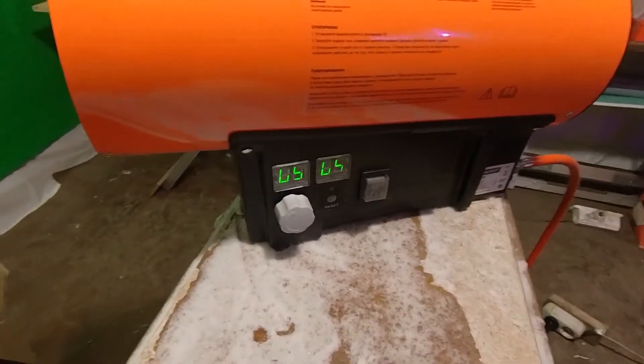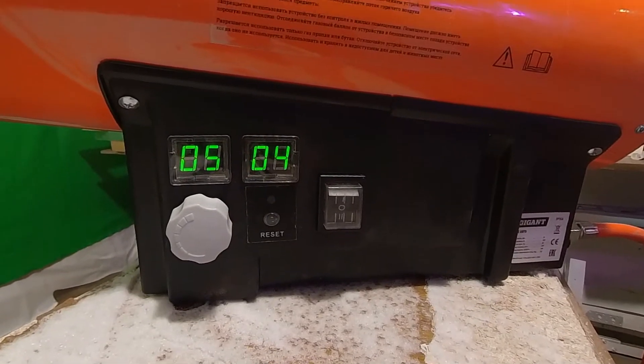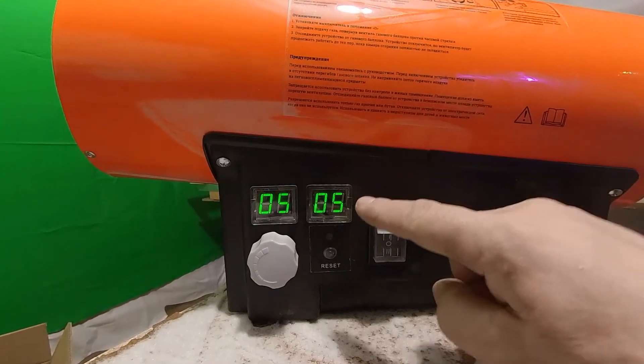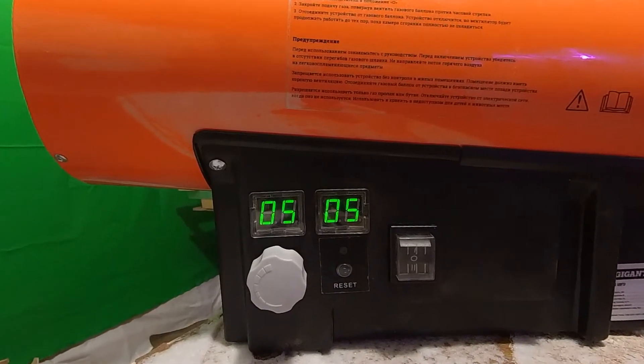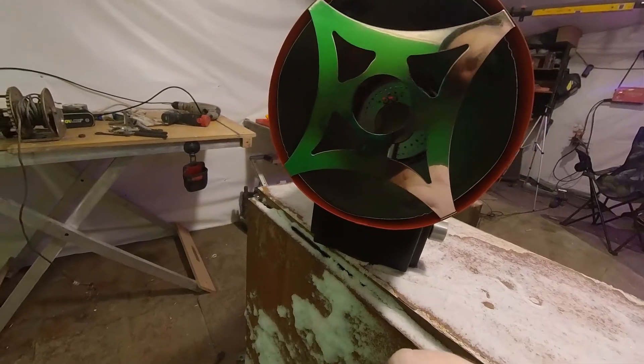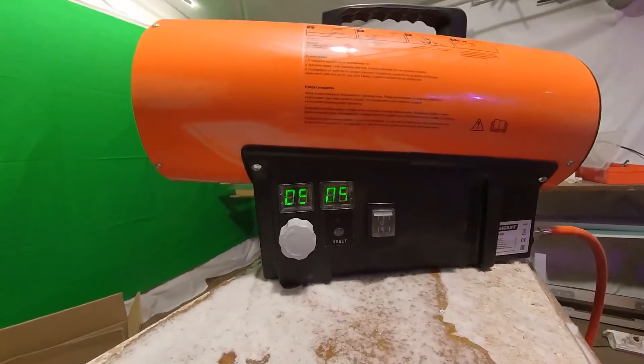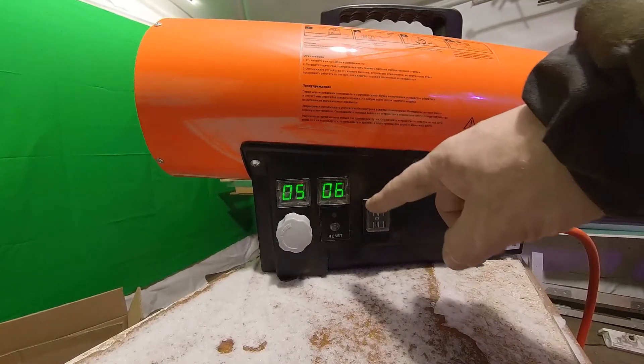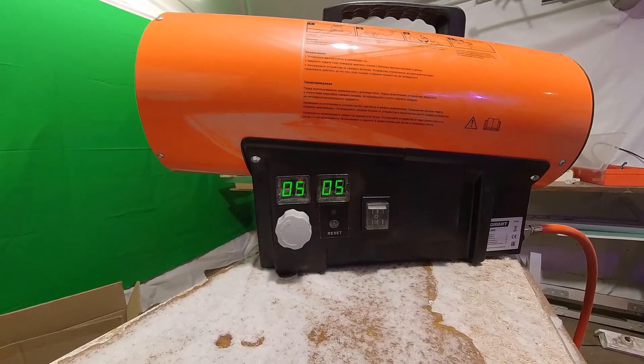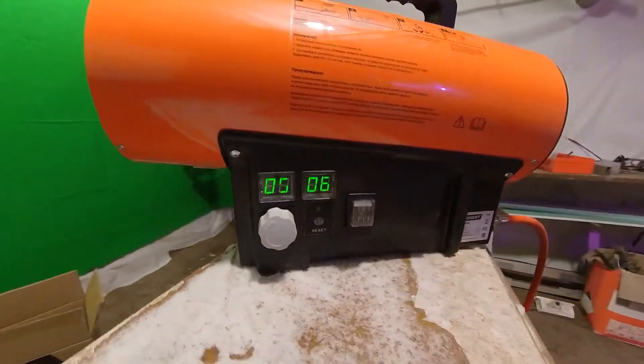The temperature is already 5 degrees — we're waiting for the shutoff. When it rises by one degree it will turn off. The temperature has reached 6 degrees and the heater has switched off. The fan continues running for a while to cool down the unit. At 4 degrees the heater will turn on again. Now it has fully shut off — we wait for it to restart automatically.